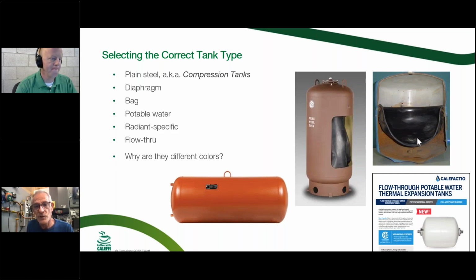Now the one in the middle, some of those you can pull that bag out and replace it if it ever went bad. I don't know if anybody's ever done that. There used to be some partial acceptance tanks like in the middle, where that bag wasn't the full size of the tank, for a little less cost. I know when Jody did this for us about 10 years ago, there were some of those. But again, you didn't have the full acceptance volume of the tank with that.